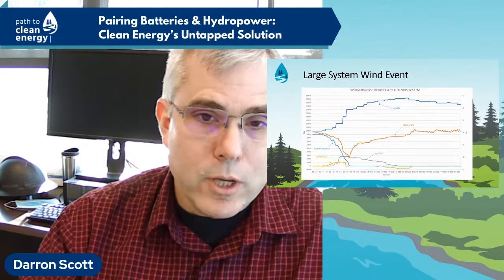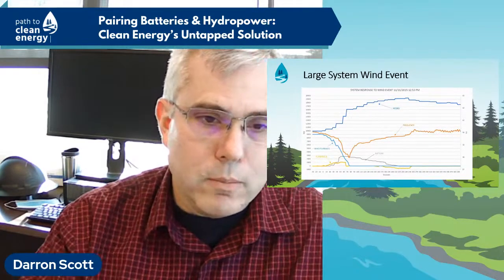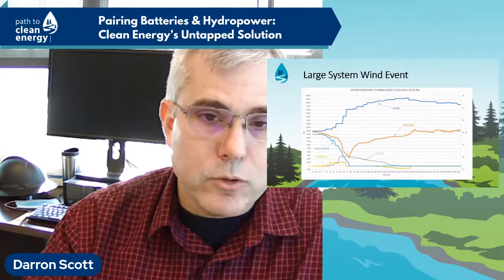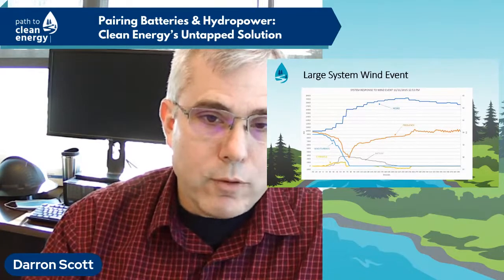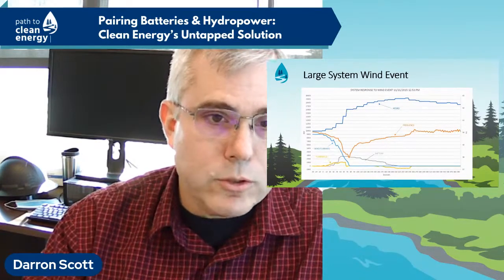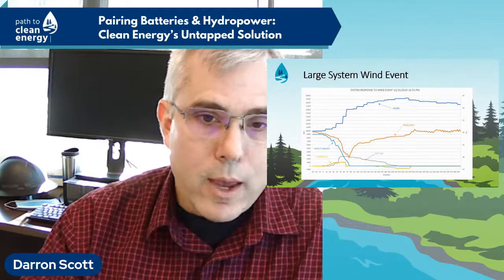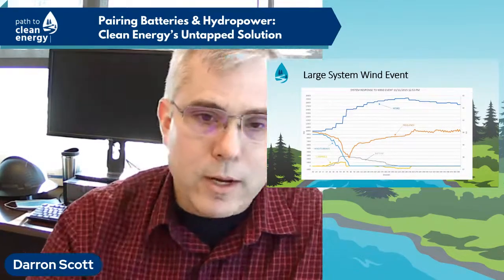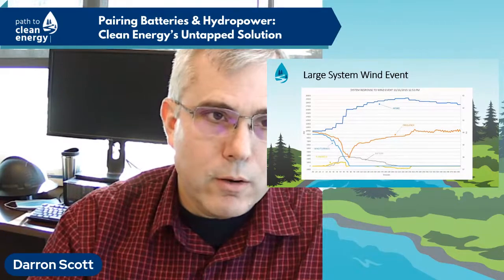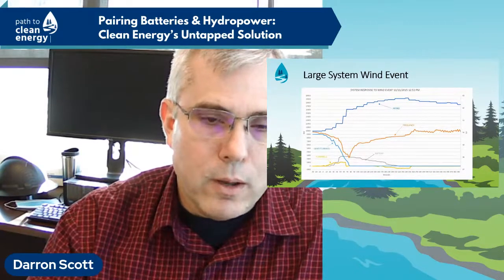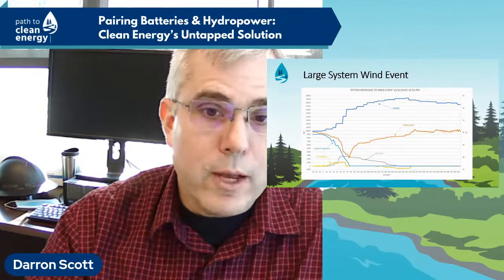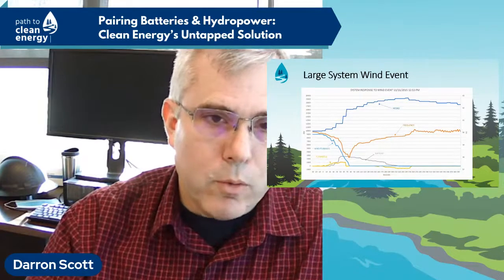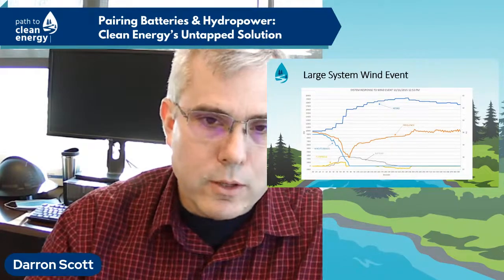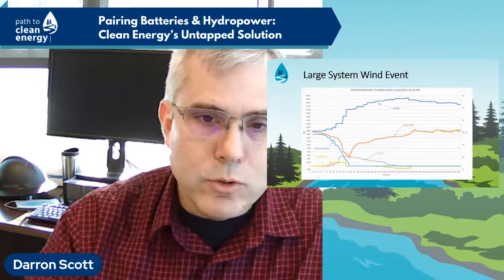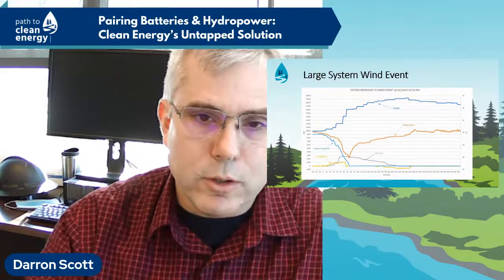The way everything is set up on our system, the batteries and the flywheels are set up in droop mode, so we have the flywheels acting first because of their mechanical ability. You can see them on the yellow line at the bottom. They came in first, but they're not much power, a megawatt each, and they don't last very long. They can go a full megawatt for 16 seconds and then drop back off. These are detuned a bit to last a little longer, as you can see on the graph.